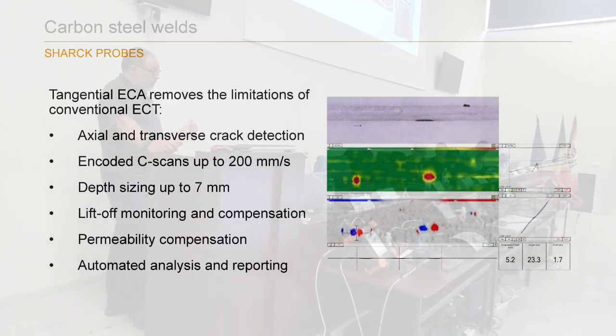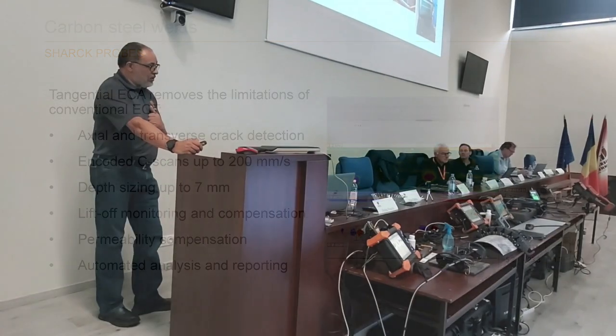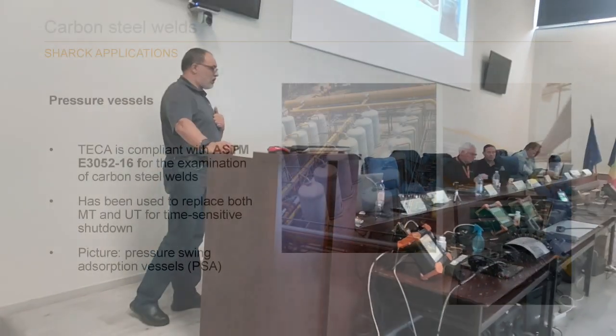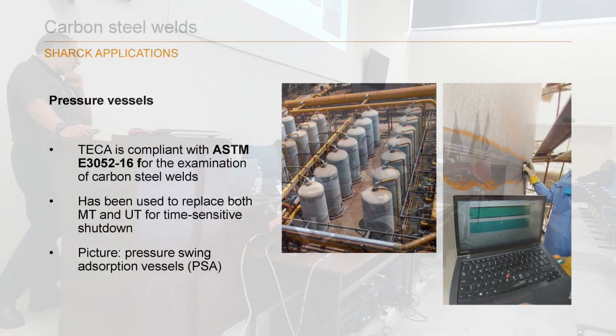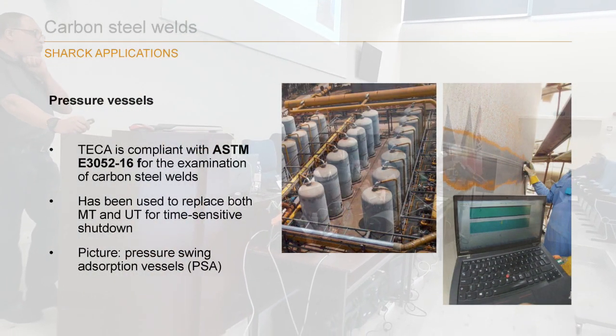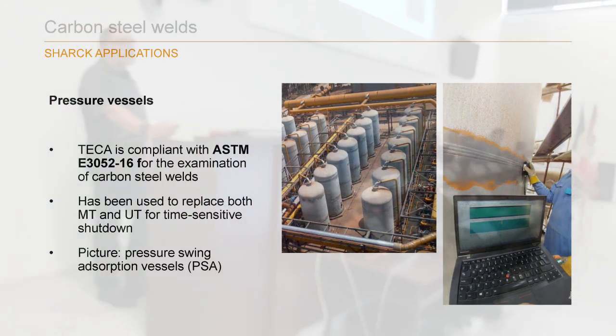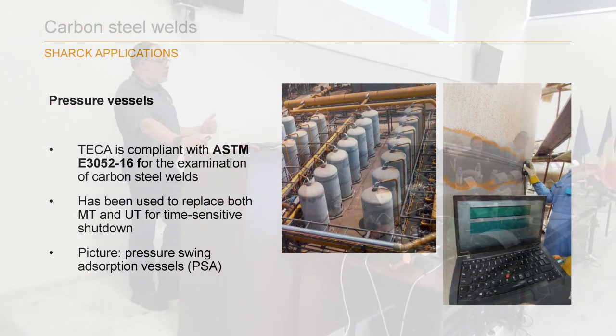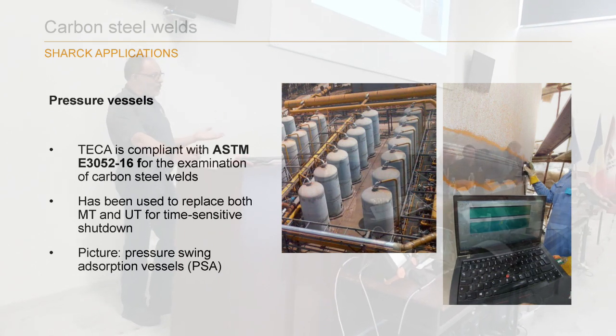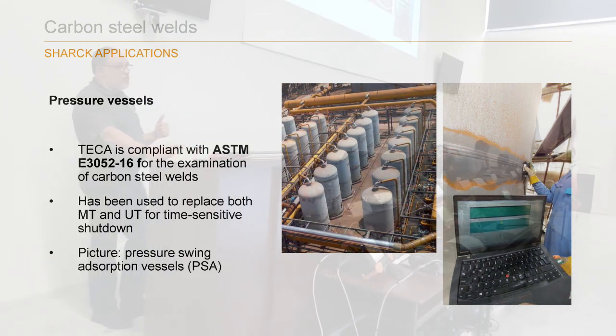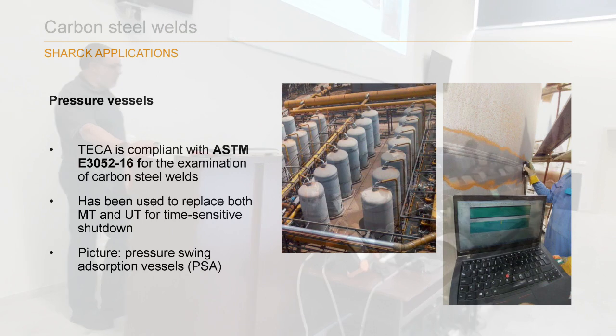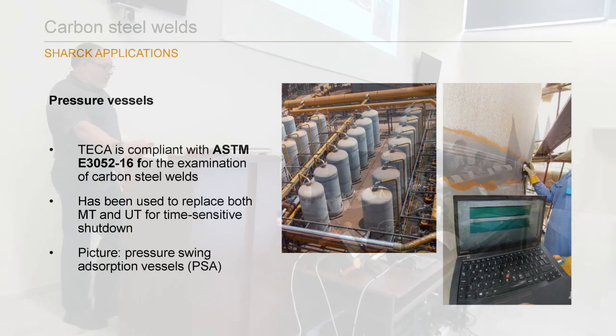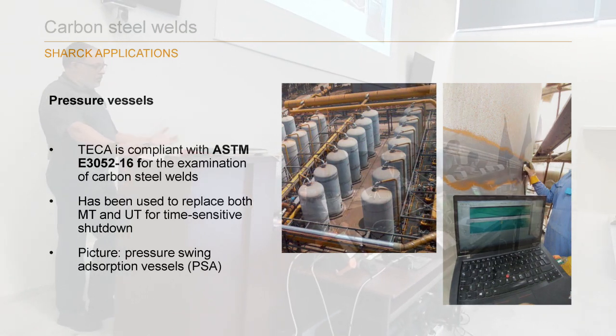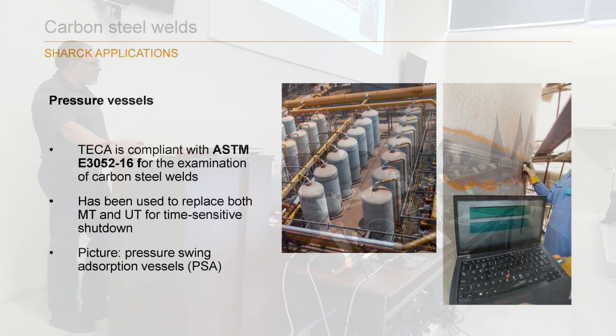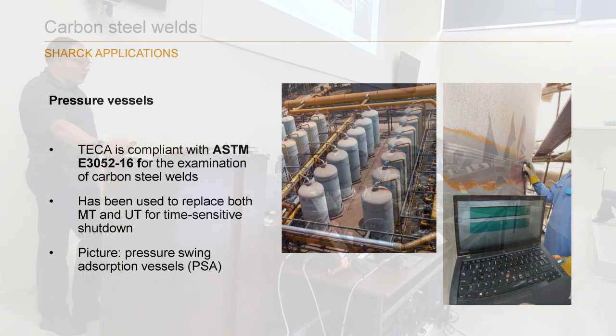This technology is compliant with ASTM code. The most difficult challenge we're facing using Eddy Current Array is the applicable standards. ECA has been introduced recently in the ASME code, but we're still lacking some ISO standards. Hopefully it will come in the near future, and then you'll be able to use a real standard and compliant code for your applications.